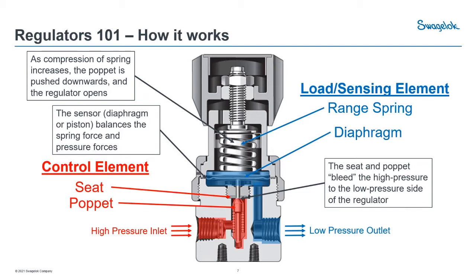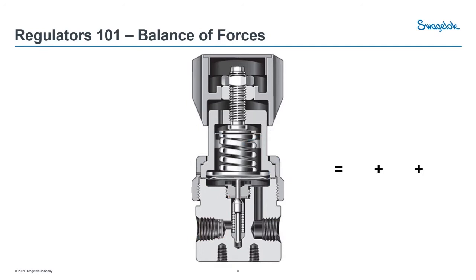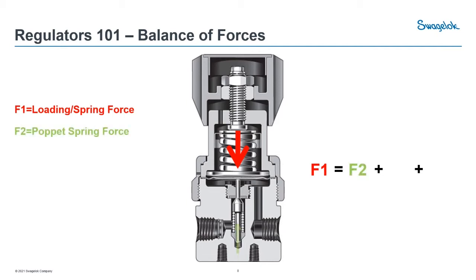The self-actuating part is reliant on balancing of forces. F1 is our loading or spring force, which is dependent primarily on the spring rate and the amount compressed by the adjustment knob. F2 is our poppet spring force, dependent on the spring rate of that poppet spring — this will generally slightly increase as the poppet starts to open.